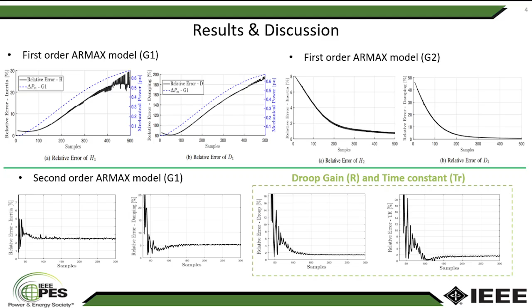And the results show that the frequency response parameters, inertia, damping coefficient, droop gain, and time constant of the regulator can be estimated using the second-order ARMAX model with relative errors below 5%. On the other hand, the first-order ARMAX model has its application reduced to inertia estimation in a specific data window.